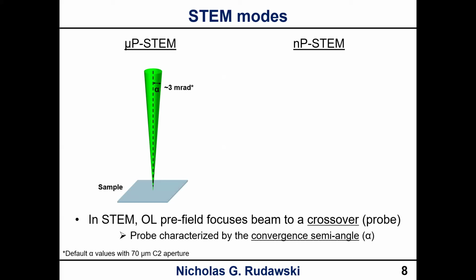So the default value with the 70 micron C2 aperture on our Themis Z microscope is 3 millirad. Now, in the software, it says 1.5, but that's not accurate. I've measured it. It's about 3. So the alpha value in microprobe indicated in the software is not accurate. That's important to note. It is accurate in nanoprobe mode if you do the condenser calibration properly, but it's not accurate in microprobe mode. Anyways, a little bit of a side jaunt there.